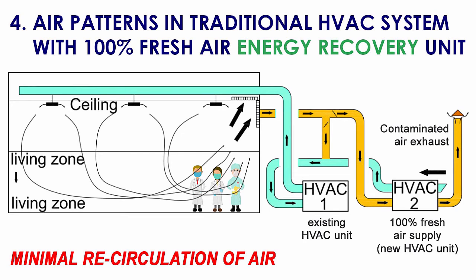Here, the air is dropped in the living space and it is a high percentage of fresh air, so the contaminated air in the living space is diluted and the air with the contaminants is moving toward the high return grills. As this air has a lot of fresh air and the contaminated air is highly diluted, the percentage of contamination in the air that rises to the high grills is low. So the risk for medical personnel to get infected is low.